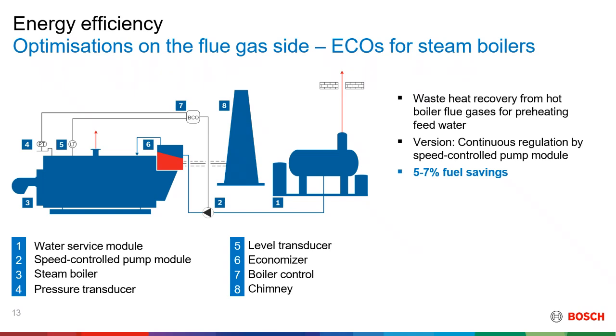This setup on the screen shows a setup of a pump which has speed control. So the pump will be able to modulate the amount of water that is flowing into the boiler and into the boiler through the economizer. Next slide. Yeah, I don't know if you want to ask if there's any questions at this point.